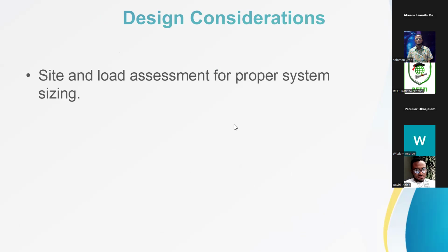But for C&I, there's what we call the energy logger. You need to log the facility for a minimum of 7 days. When you log it, you get a CSV file, and from that file you get your peak load and your average load, so you can do a proper sizing and design.